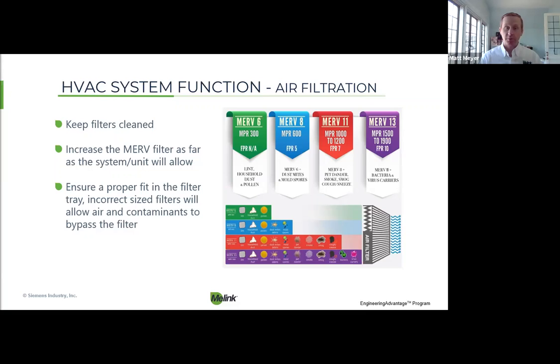But the increase of your MERV filter really needs to be, and I think Jeremy's going to talk about this too, you've got to weigh the pros and cons between how much MERV or how much restriction my filter can allow before I start using too much energy on my unit. That's a very important factor here. So what we're trying to suggest here is increase that MERV filter as much as your system will allow you to do that. You could have a building where you've got 4 different types of RTUs. Half of your RTUs can all take a MERV 13 with no problem, just had to do a little bit of a speed increase on your fan. But then your other ones, they're already maxed out. They're already near their FLA. If you try to increase any more restriction, the static's going to be too high, and you're not going to be able to do that. It's not going to be good for your equipment. It's going to end up breaking. So you've got to weigh that balance.